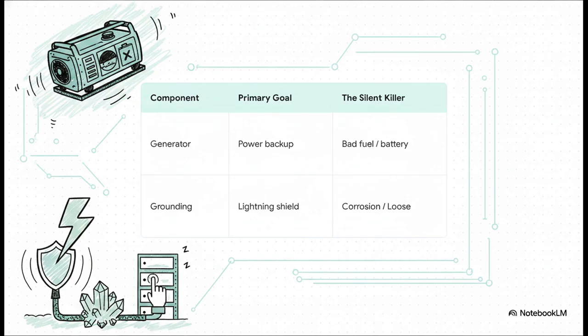Take the generator. It needs weekly auto-start tests because something as basic as a dead starter battery or contaminated fuel is its silent killer. And then look at grounding, which is your invisible shield. In humid, salty air, like out in the coastal areas of Ajman and Dubai, ground connections can quickly corrode with this green and white crust. If a technician touches a rack and feels a little tingle, that grounding has failed. It means the stray electricity meant to travel safely into the earth is now traveling through the equipment and potentially right through the technician.